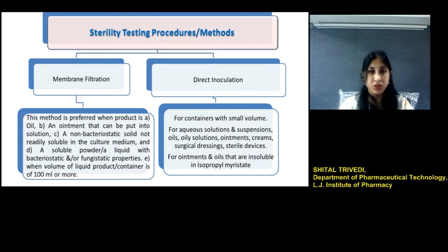The membrane filtration method is preferred when the product is an oil or an ointment that can be put into solution form, or a non-bacteriostatic solid that is not readily soluble in the culture medium, or a soluble powder or a liquid that has bacteriostatic and/or fungistatic properties, or when the volume of the liquid product in a container is 100 ml or more. So for large volume containers, this test is preferred.